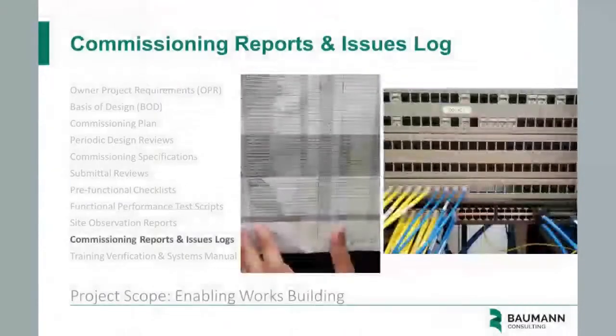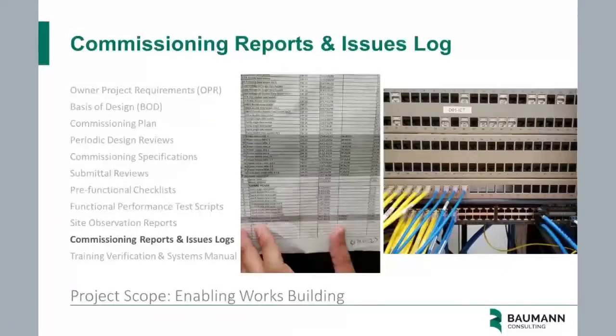Slide 31 real quickly. In real time, as well as checking on the BMS communications, there's the communications link from the control panels to the BMS interface that was also verified using the checklist, which is a picture on the left. And on the right were the ICT connection points in real time, making sure that what you have on the left actually matches with what you have on the right.